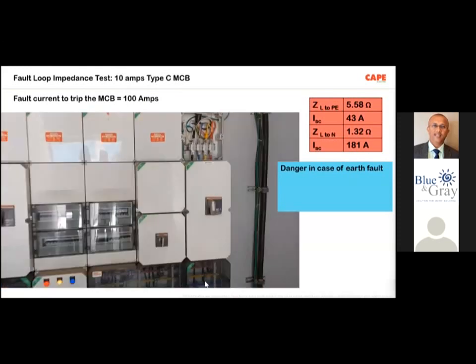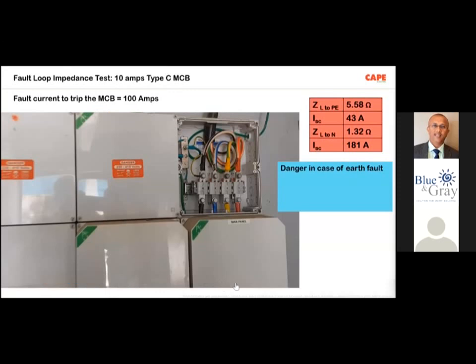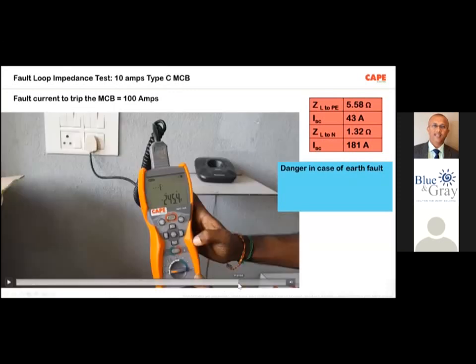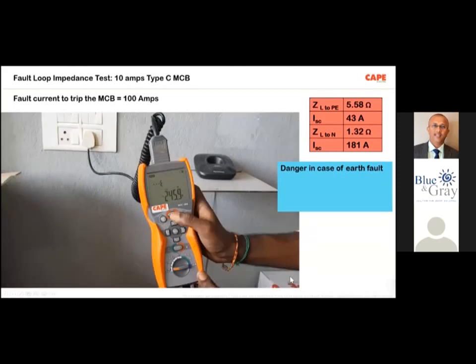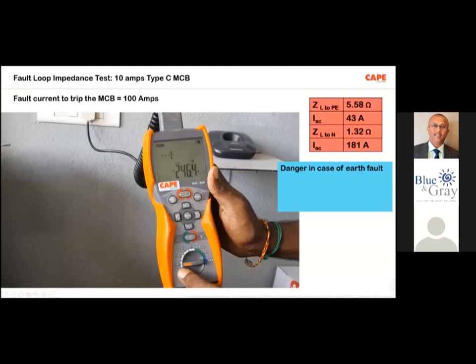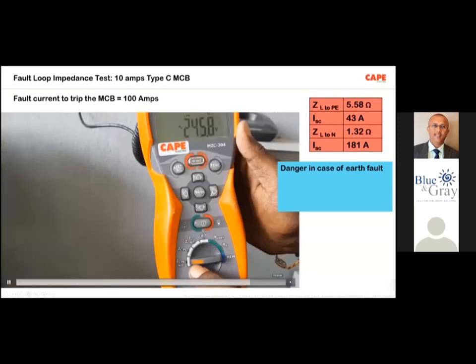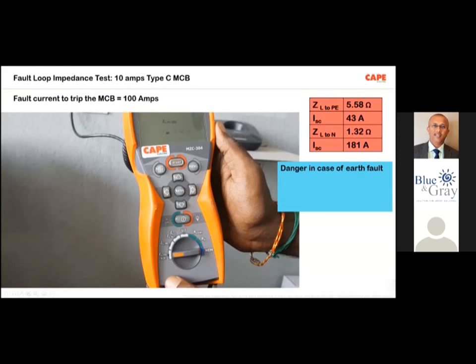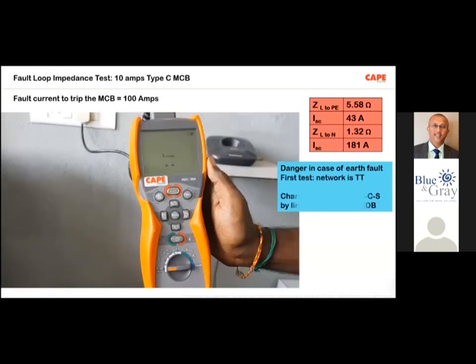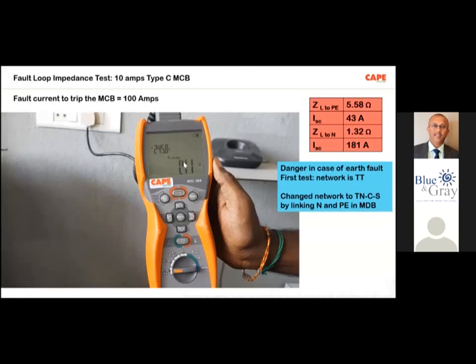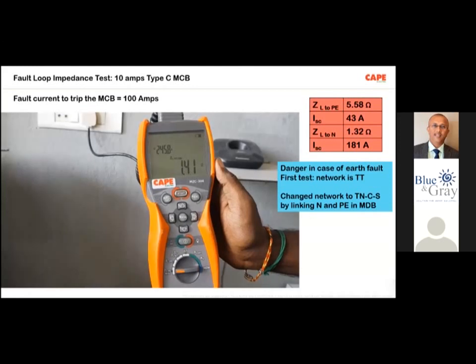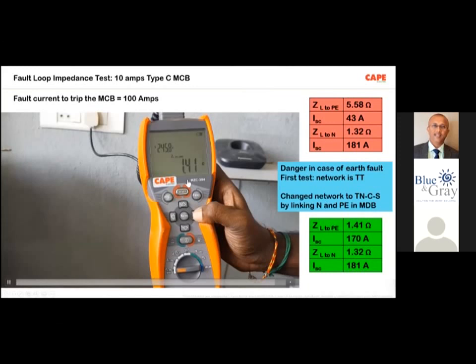Now, I will skip a little bit. We have to change the system to a TNCS, but after seeing my video, a lot of people try to do it on their own and end up in trouble. So I don't want to show how this is carried out. We changed the network to a TNCS network. Then we are doing the test. Now you see the values here. The fault loop impedance is 1.41 ohm, the fault current is 170 amps, more than 100 amps, which is enough for our MCB. We are sure that our MCB is tripping.